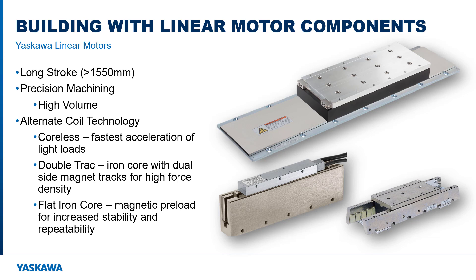While Yaskawa does not provide custom designed linear stages, this can be accomplished in-house or through a third party. Some customers are capable and experienced enough to precision machine and assemble a linear motor. If they also have a demand for a high number of units, it may make economical sense to fabricate a custom linear motor stage in-house. Additionally, some applications may benefit from Yaskawa's alternate motor coil technology. The coreless motor offers the fastest acceleration of light loads, and the Double Trac iron core technology packs more force in a smaller package. These technologies do require a custom design, as the Sigma Track 2 exclusively uses the flat iron core.